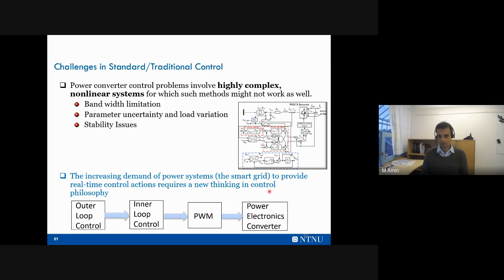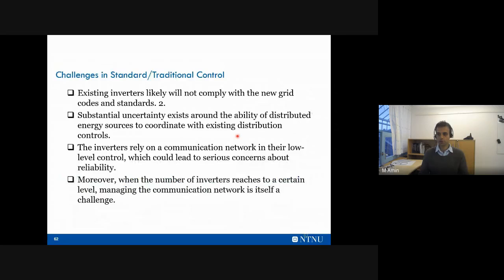Another issue is that wind power is injected directly into the grid regardless of grid conditions, which is a major limitation, and it does not comply with grid codes. Traditional generators participate in regulating voltage and frequency, but the standard generator control systems we use now do not. So we need a different control approach that can regulate voltage and frequency.